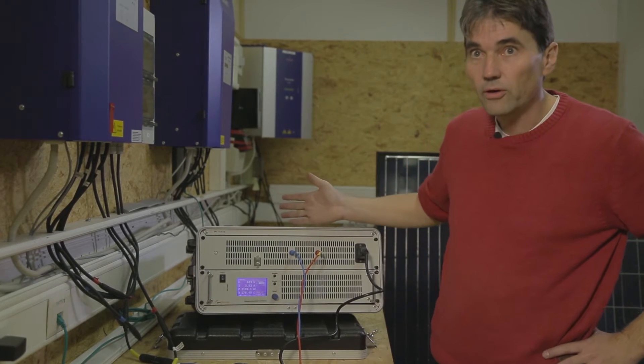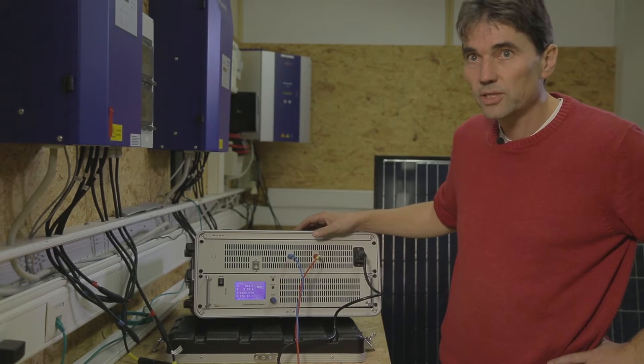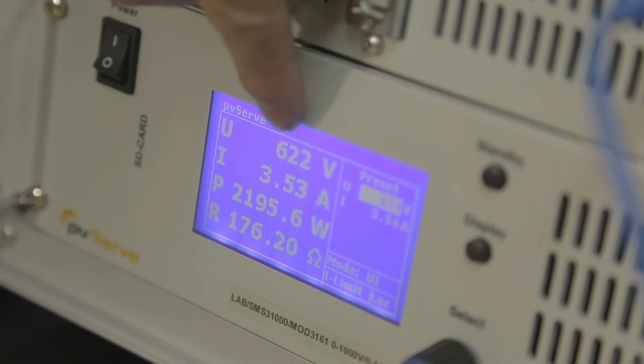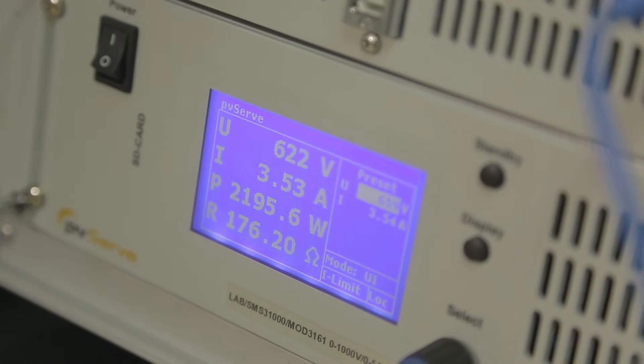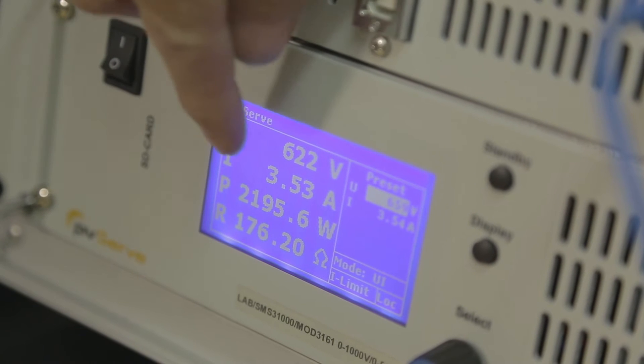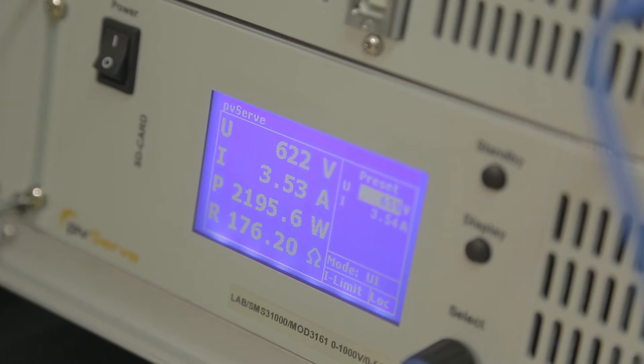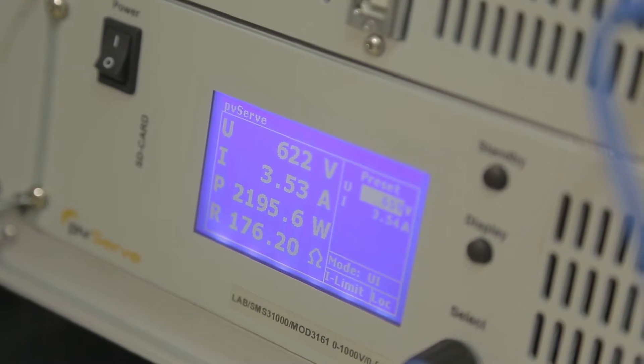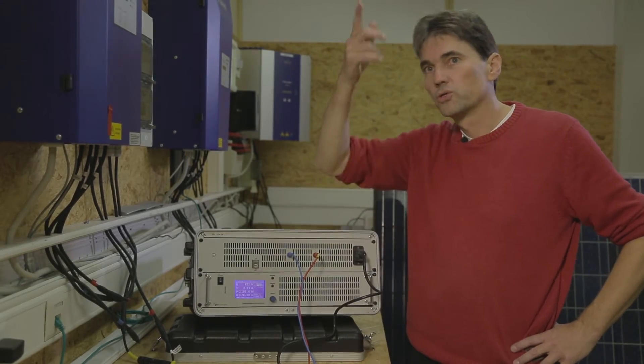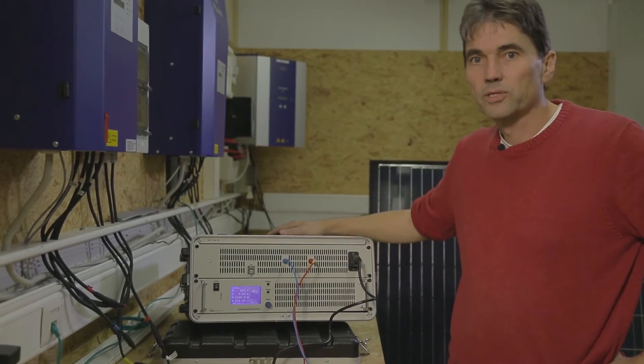The sound of the fan tells you that the device is in operation. Here, you can see 622 volts, the voltage needed to send current back through the solar generator at 3.53 amps, which you can see here. That allows us to conduct these investigations on a roof.